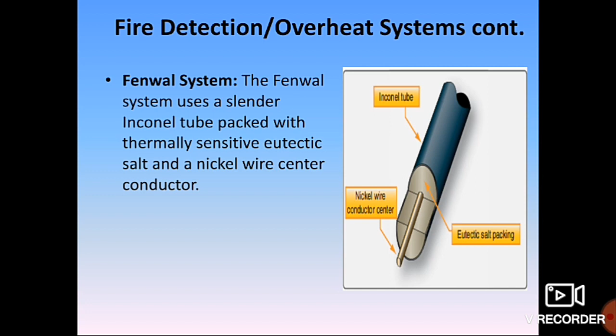of the aircraft system along the element length, the resistance of the eutectic salt within the sensing element drops sharply, causing current to flow between the outer sheath and the center conductor. This current flow is sensed by the control unit, which produces a signal to actuate the output relay and activate the alarms. When the fire has been extinguished or the critical temperature lowers below the set point, the Fenwal system automatically returns to standby alert and is again ready to detect. This is all about the Fenwal system.